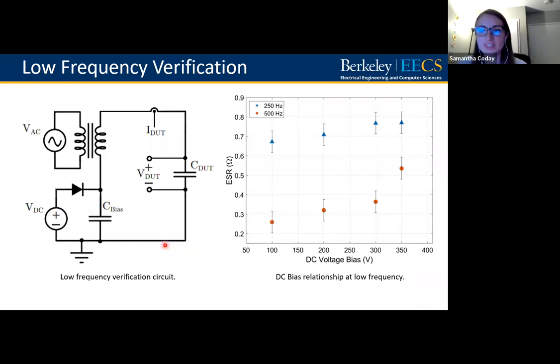We wanted to do one more sanity check before moving on, because this was important data. We were finding that the ESR was two times what it was at 0 volts, so we wanted to verify that. Previously I said we couldn't do electrical measurements because of accuracy issues at the frequencies we wanted to test, but we can do an electrical measurement at much lower frequencies. So while 500 hertz still isn't low for most people, for the switched cap world it's pretty slow. We did these electrical measurements, and the accuracy still isn't great, we have fairly large error bars, but we performed the electrical measurement using the technique shown here.